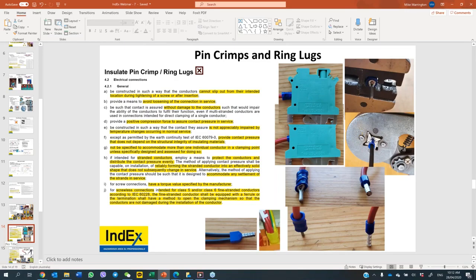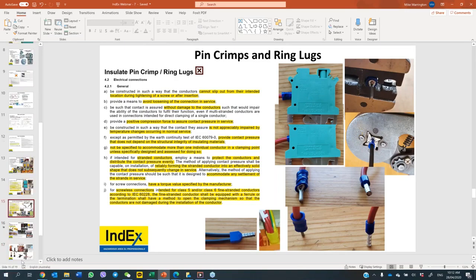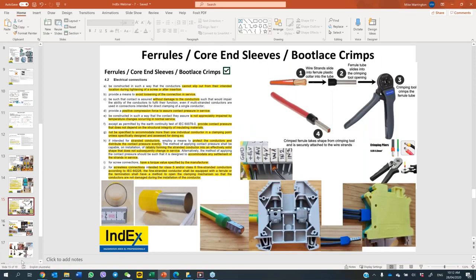4.2.1. That is 60079-7. It mentions the word ferrule and core end sleeve, and the conductor not being damaged, the conductor insulation not being damaged, and the insulation of the ferrule not being damaged. Well, everything I just said, the insulated pin crimp does damage those things. So people can disagree, but it's clearly defined in the standards. It's just that people usually don't want to read. There's a lot to read there.